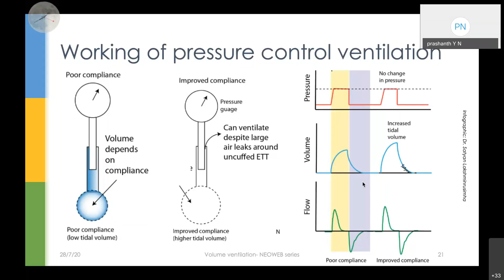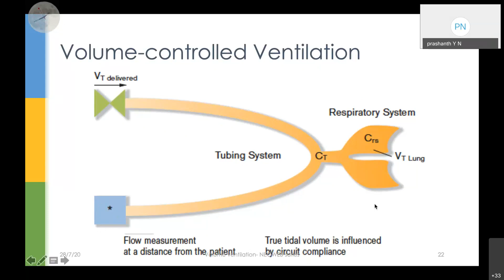So let's see what volume control ventilation is. In pressure control ventilation, we talked about the pressure which is controlling the volume. Here we are talking about volume directly. What happens in volume control ventilation is that a set tidal volume is delivered into the tube. That's all. This traverses, and obviously it will go to the baby's lungs, and then at the end of the expiratory limb towards the ventilator, you measure your flows. So we are just pushing the gas inside without looking at what is happening in the lungs.